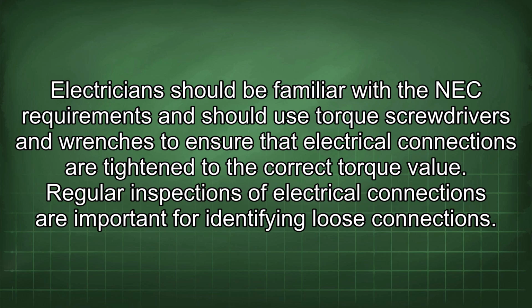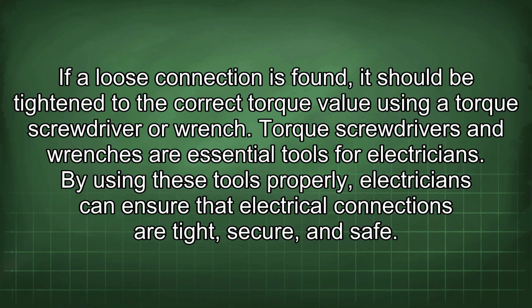Electricians should be familiar with the NEC requirements and should use torque screwdrivers and wrenches to ensure that electrical connections are tightened to the correct torque value. Regular inspections of electrical connections are important for identifying loose connections. If a loose connection is found, it should be tightened to the correct torque value using a torque screwdriver or wrench. Torque screwdrivers and wrenches are essential tools for electricians. By using these tools properly, electricians can ensure that electrical connections are tight, secure and safe.